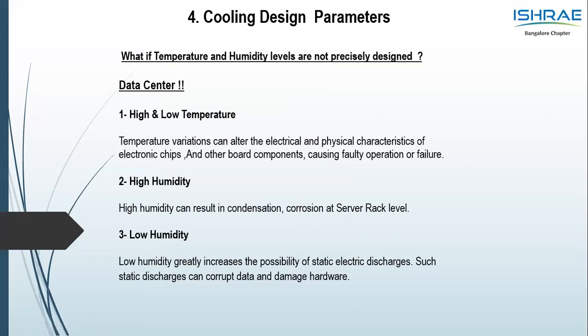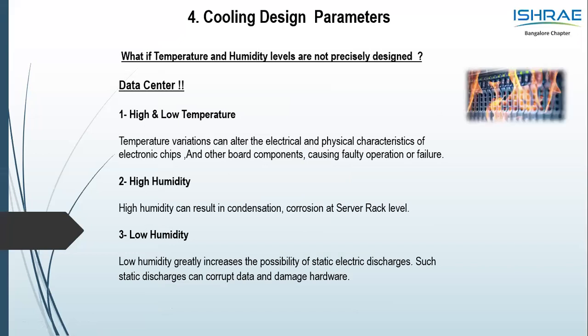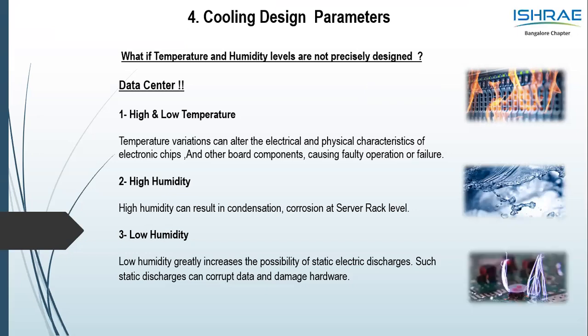What happens if the temperature and humidity are not precisely designed? Very high temperature, yes, can hamper the server, thereby there can be a loss of data. I think you would have seen the video or article, the data center which caught fire in France. Of course, it was due to a fire, but very high temperature can hamper the server rooms and data center. We don't want very low temperature. Why? Because cooling units have to work more, thereby your power consumption would also increase, thereby your operational cost would also increase. Very high humidity, we don't want that to happen. Condensation can happen at the server level. Low humidity can generate static which can affect the server, thereby causing a failure. So a precise control and bracket of temperature and humidity is what we will have to maintain. What are these temperatures? We will look at it in the coming slides as I talk.